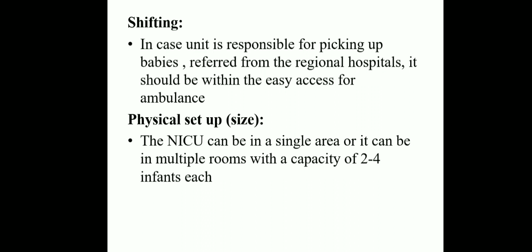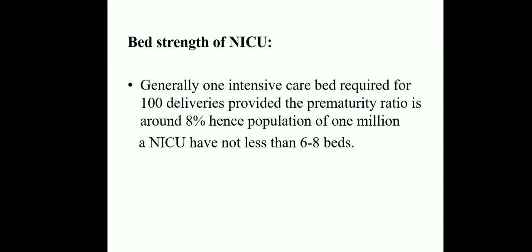Next is physical setup, that is size. The NICU can be a single area or multiple rooms, with a capacity of 2 to 4 infants in each, regarding bed strength of the NICU. Generally, one intensive care bed is required for 100 deliveries, provided the prematurity ratio is around 8%. Hence, for a population of 1 million, a NICU should have not less than 6 beds. Minimum NICU bed strength is 6 to 8 beds.